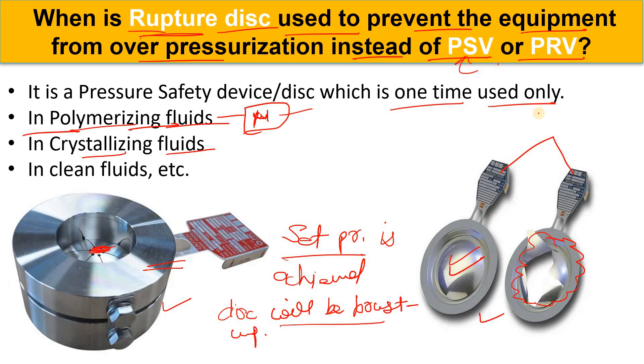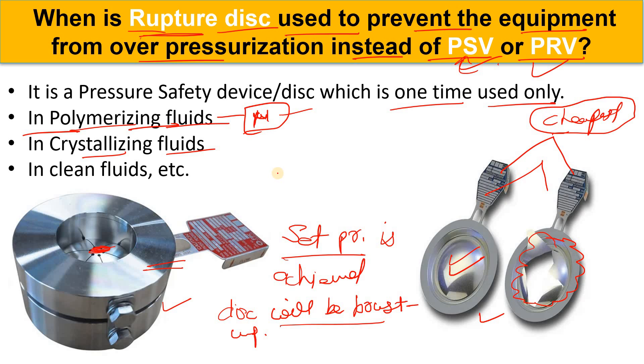Whenever we have to prevent our system from over-pressurization, the rupture disk is the cheapest option available. Only if we cannot use the rupture disk do we go for the PSV or PRV. These rupture disks are designed at a specific pressure so that when that pressure is achieved, the disk bursts. They are also calibrated and tested before use.